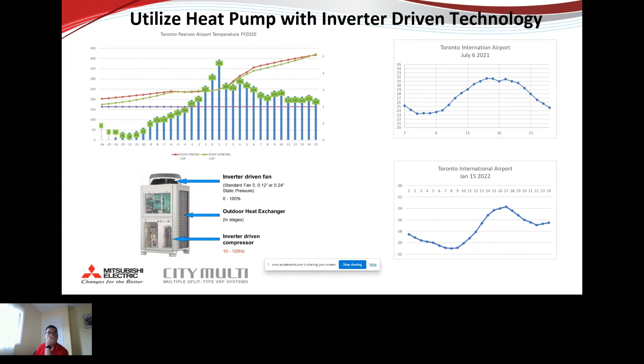So coming back, we are using VRF to provide heating and cooling, and how much heating and cooling you are using is also managed in the background. So let's say on October 10th I want heating and you want cooling. Right now outside is, let's say, 10 degrees C, and I want heating, you want cooling. So the condenser will shoot out a liquid gas mixture, and the branch box will separate the liquid and gas. So liquid goes to the place that needs cooling, and gas goes to the place that needs heating. Obviously, it goes a lot deeper than that, but feel free to reach out to me if you have further questions, or reach out to Mitsubishi Electric so we can talk more about those controls.